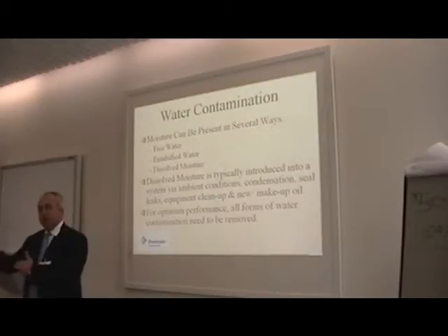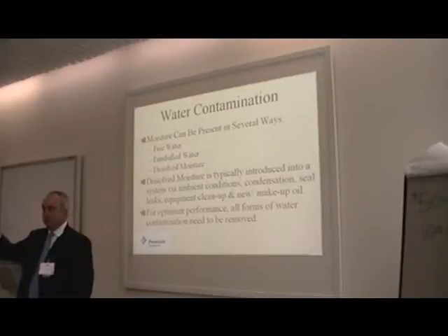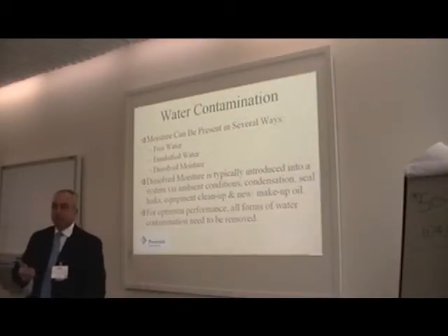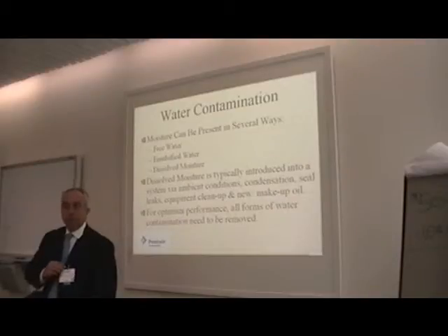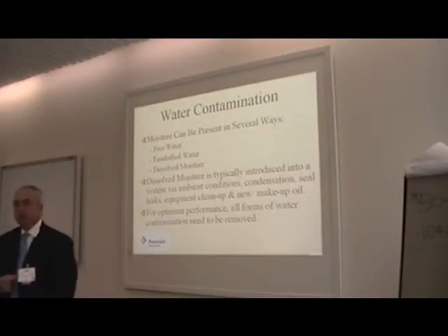So they had a threshold of 1,000 cutoff, although when we called their technology leader at corporate, he said, no, it's 300. Like, you guys don't even have the tools to measure it. So it was an interesting experiment, but the beauty is the technology for dehydration got them down, within 2 weeks we were at 30 ppm. After that it went down to 20. No reason it won't stay there.